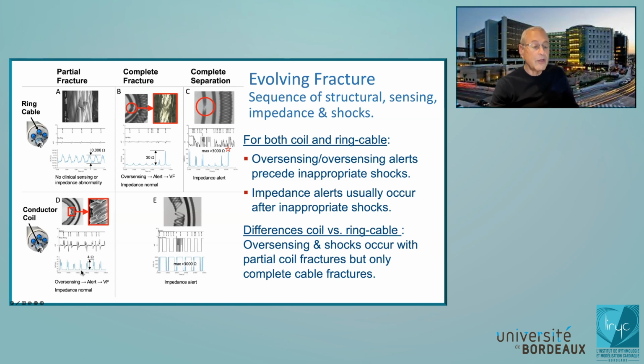On the other hand, with a conductor coil, we have oversensing that led to inappropriate therapy, and the maximum change in impedance is 4 ohms, which you'd never notice in a pace sense conductor.